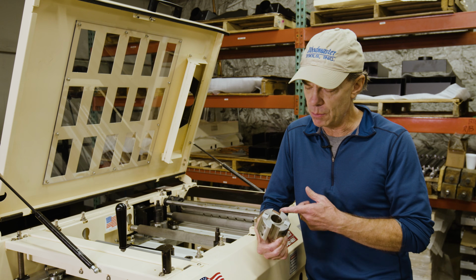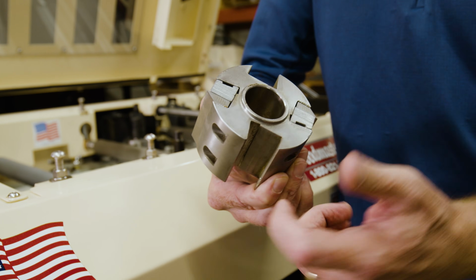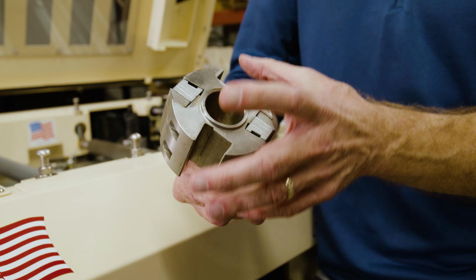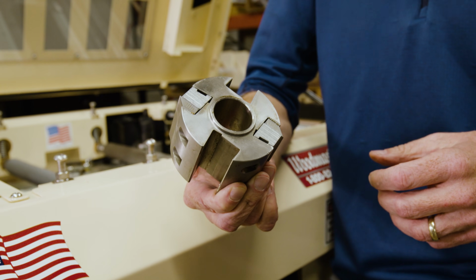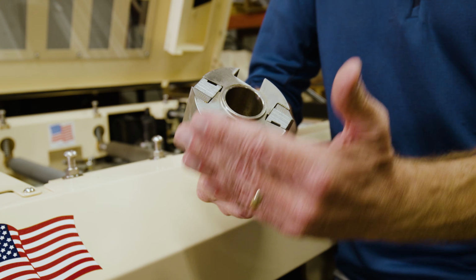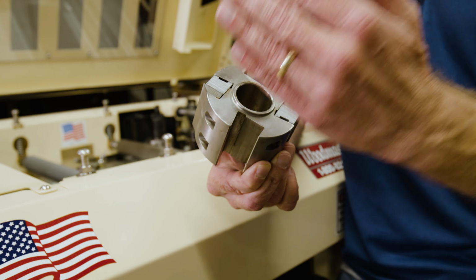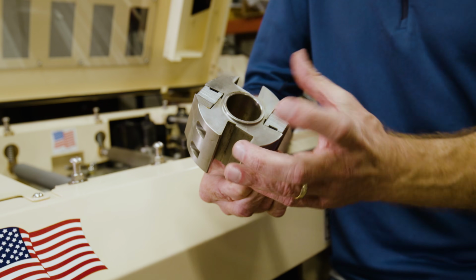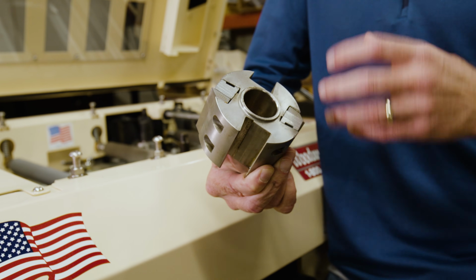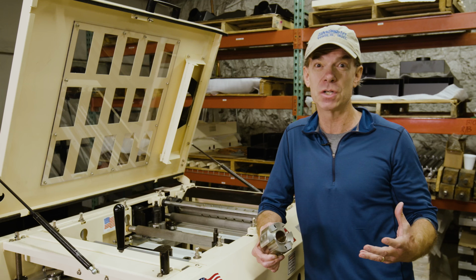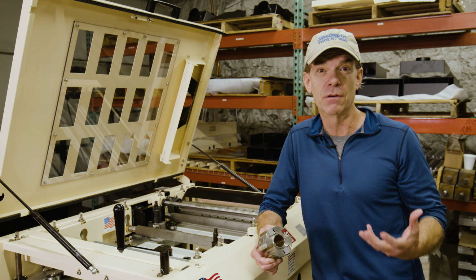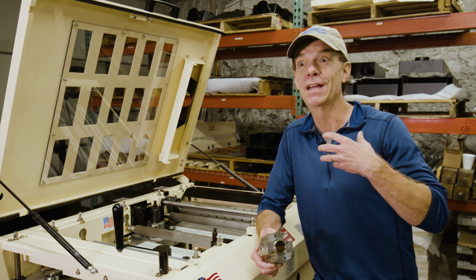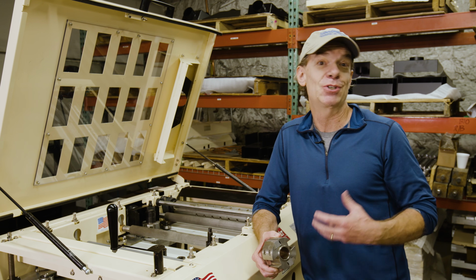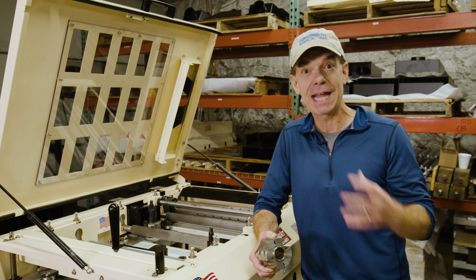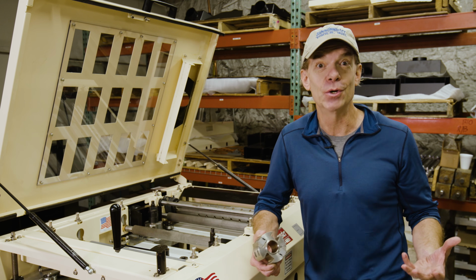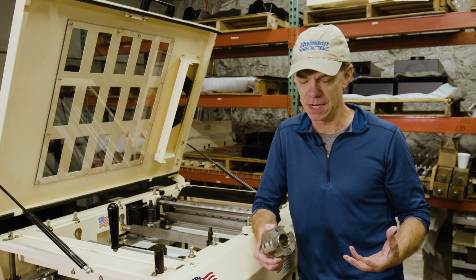The other thing I love about what we do is we have corrugation on our knives, and that's important for 2 reasons. First of all, it makes calibration much easier because you have multiple knives. When you have 2 knives, those knives have to be sticking up the same amount. When you have corrugation, you're able to calibrate them with each other much more easily. And actually, calibration in general, we're going to see, is an advantage of our machine. Again, that saves you time. It reduces mistakes. It's just an advantage. If you can get your machine set up accurately, more easily, that means you're doing a better job and getting a better result for your customer.